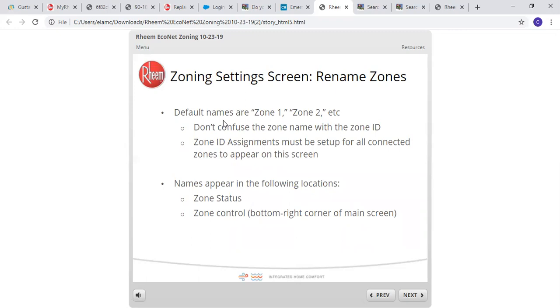You'll have your default names, zone 1, zone 2, etc. Don't confuse the zone name with the zone ID. Zone ID assignments must be set up for all connected zones to appear on this screen. So you can have your zone ID as 1, 2, 3, 4, 5, 6, but you can name your zones whatever you want to: kitchen, dining room, master bedroom, basement. Names appear in the following locations: in the zone status, and also the zone control, bottom right-hand corner of the main screen.